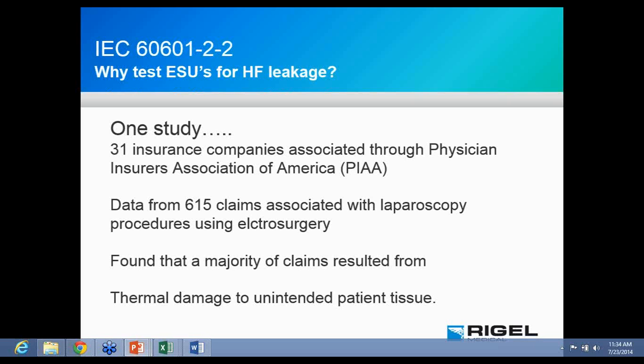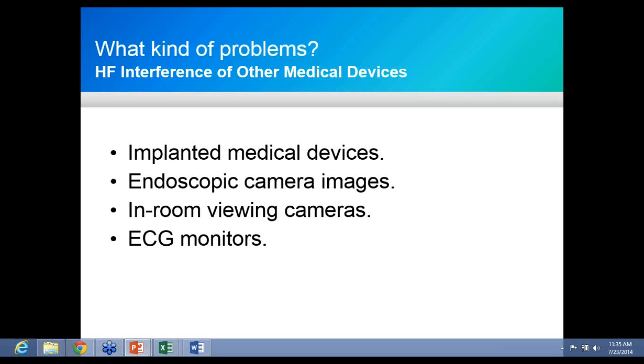What kind of problems can occur? We can have HF interference to other medical devices, implanted medical devices, class 3 medical devices. You can have problems with endoscopic camera images. About once every 6 months, someone emails me and tells me that when the ESU is being operated, they lose their endoscopic image on the ancillary monitor, not the monitor on the video card, but the one that's cabled up and goes across the room for the scrub tech to look at. And we usually find out that there is excessive leakage on that ESU. It also happens on the in-room viewing cameras, those IP-based cameras that let the nurse manager view what's going on in the room. Those are very susceptible to HF leakage.